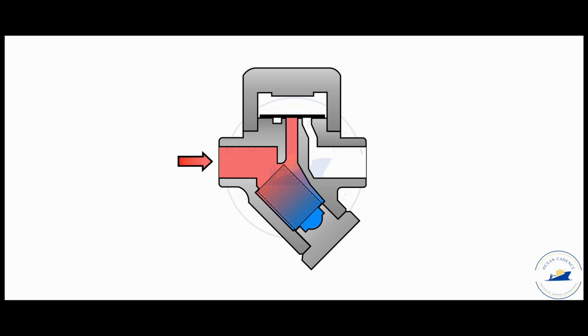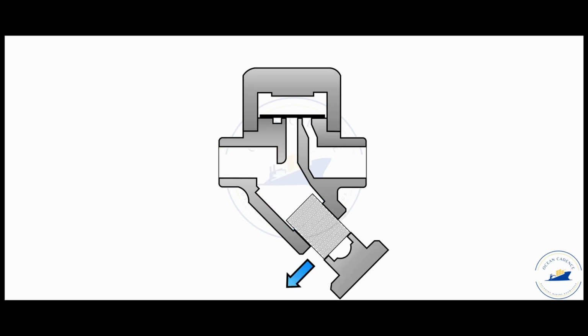Under such condition, it is imperative that after safe isolation and draining of the line, you have to open the lock nut at the bottom side of the steam trap with the adequate spanner and draw this strainer out. By drawing this strainer out, it will allow you not only to clean the strainer but also mechanically drain the cold condensate that is deposited into the line, thereby also removing the rust content and allowing you to clean the filter subsequently. After cleaning, again you have to box back this strainer and it has to be made sure that the strainer exists in the line at all points of time to make sure that the steam trap is working properly. Otherwise, it will hinder the operation of the top of the steam trap, that is the main action zone.